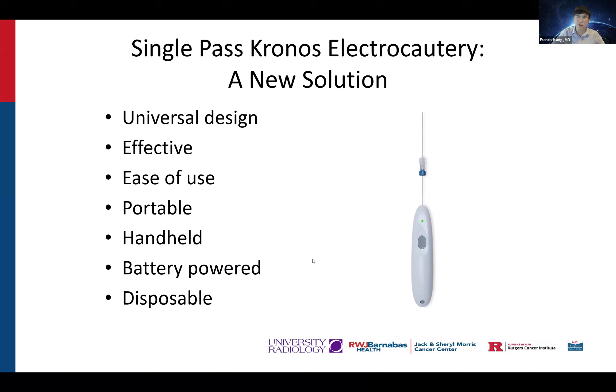A key advantage is its seamless integration into the existing coaxial workflow. It functions reliably within the same coaxial introducer needle used for the biopsy, meaning no additional punctures or excess manipulations are required. It has the FDA 510(k) clearance. It is considered a Class 2 electrosurgical device. The FDA's explicit indications for use validate the device's capability to achieve hemostasis through coagulation in liver, kidney, and lung. It is powered by 2 AA batteries.